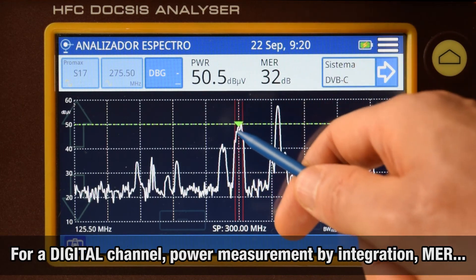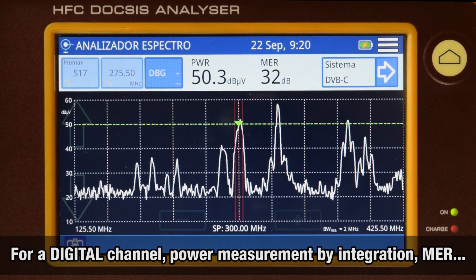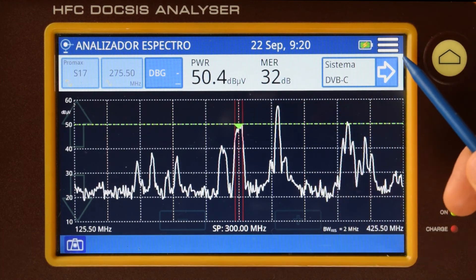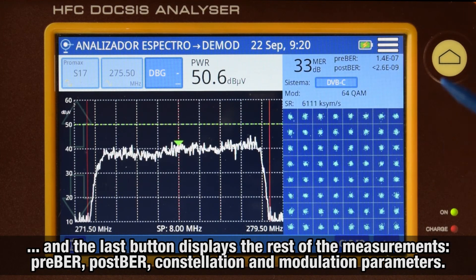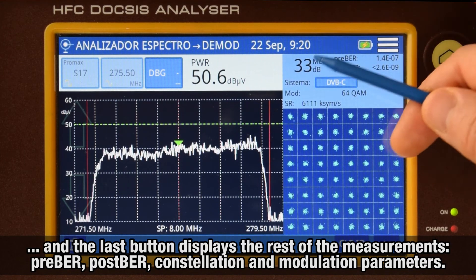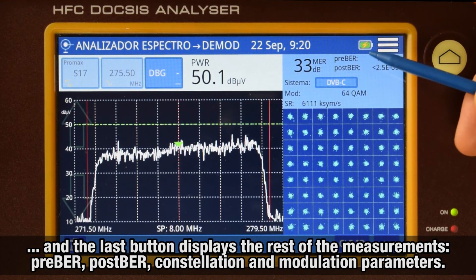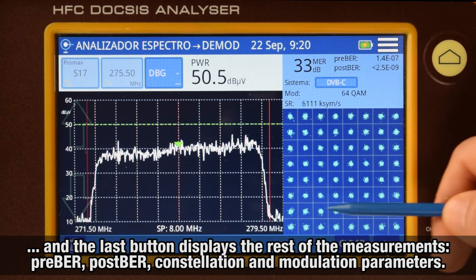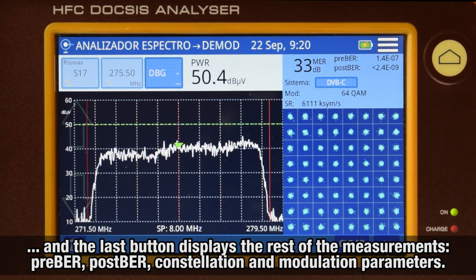If the channel is digital, we can see power level — calculated by integration — MER, and finally, by pressing the top right corner button, we can see the rest of the measurements: Pre-BER, Post-BER, Constellation, and the channel modulation parameters.